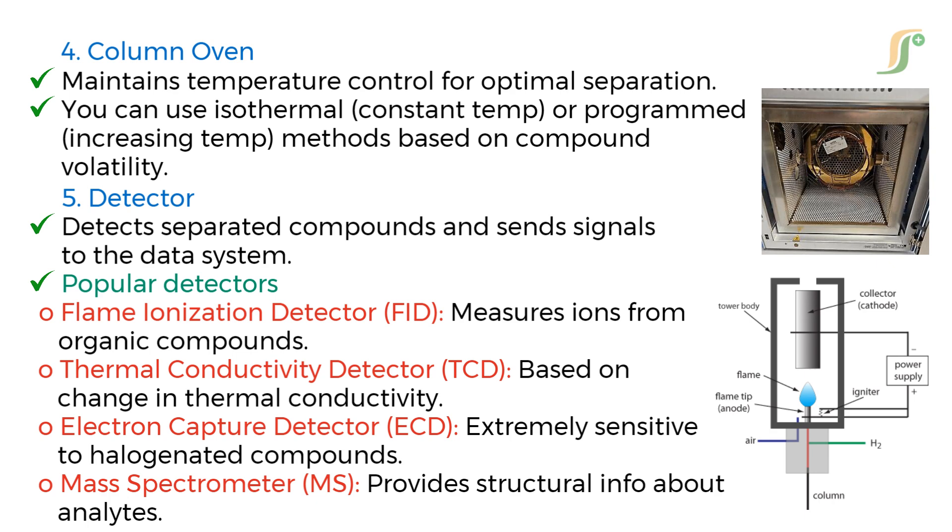Fifth component is detector. It detects separated compounds and sends signals to the data system. Popular detectors are flame ionization detector, that is FID, which measures ions from organic compounds. Thermal conductivity detector, that is TCD, is based on changes in thermal conductivity.